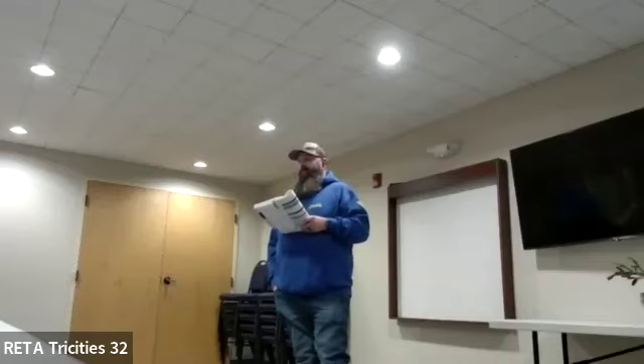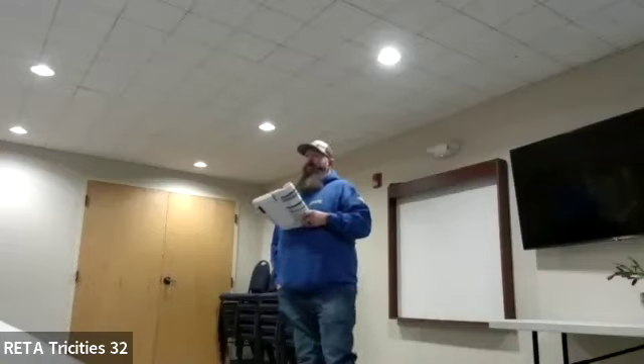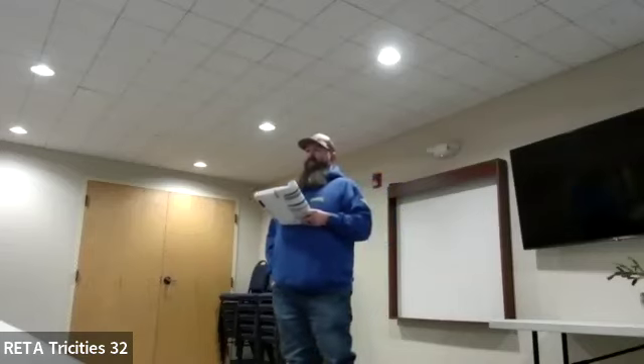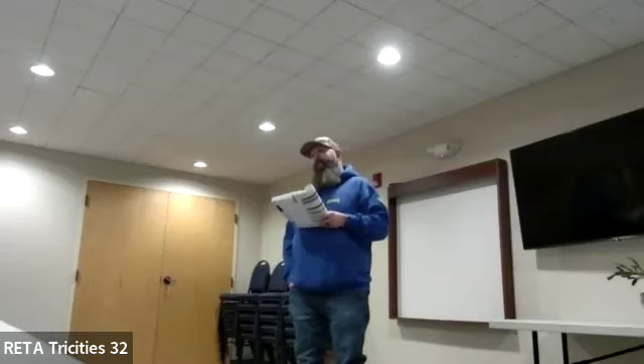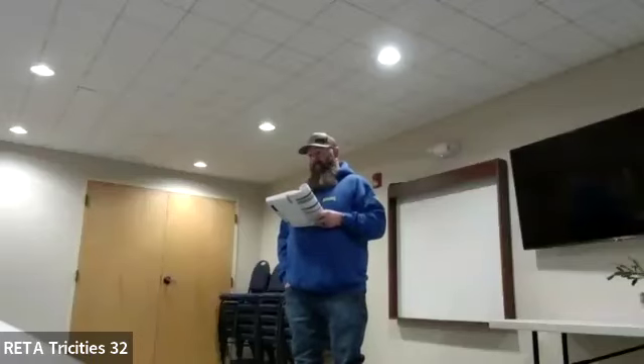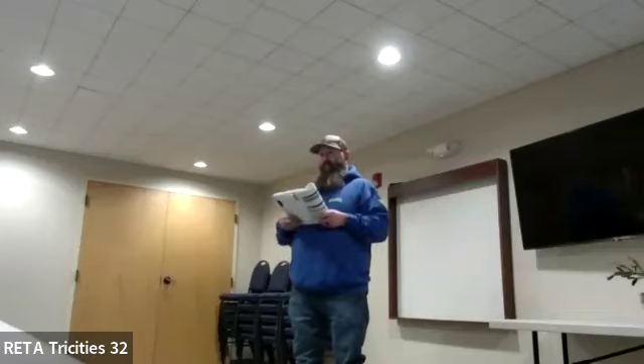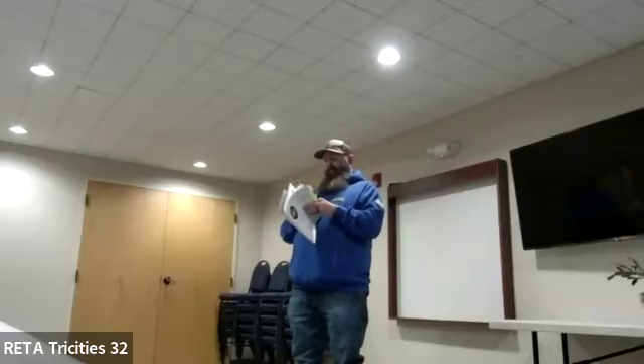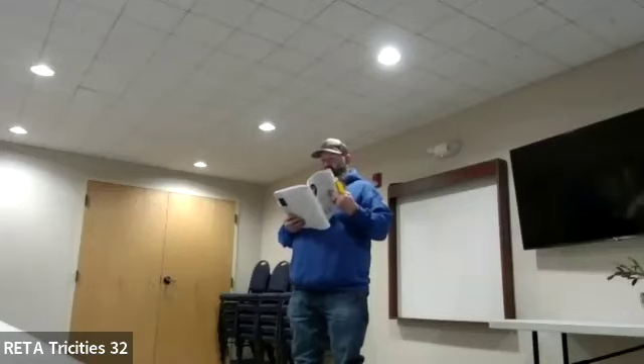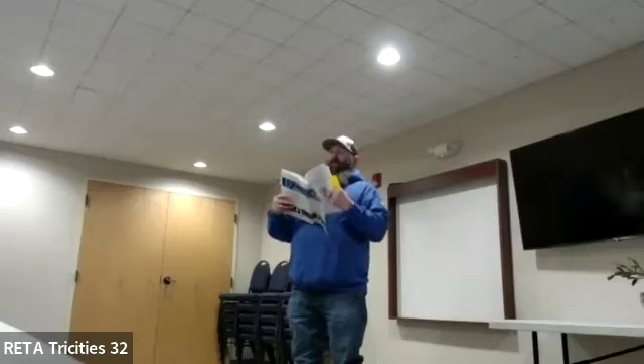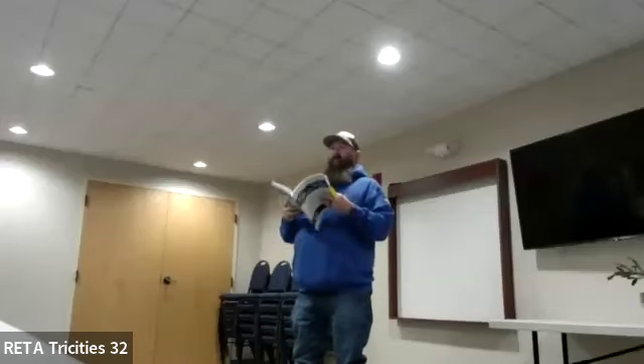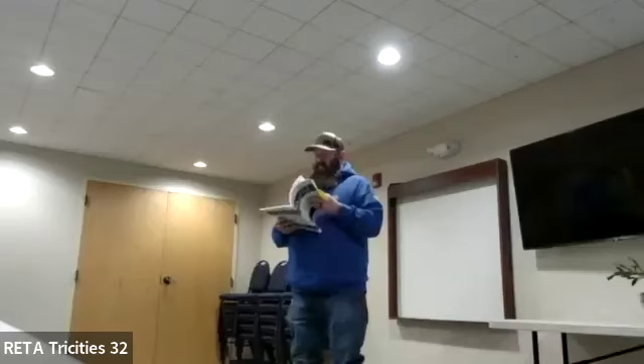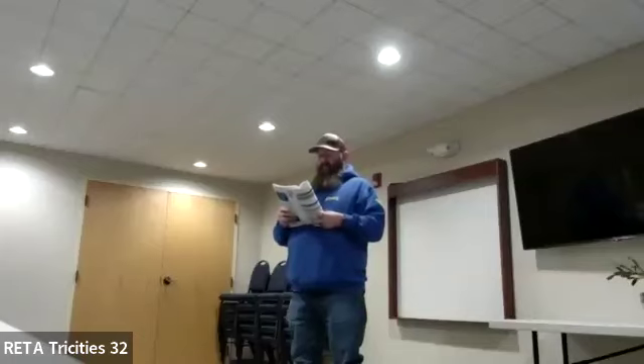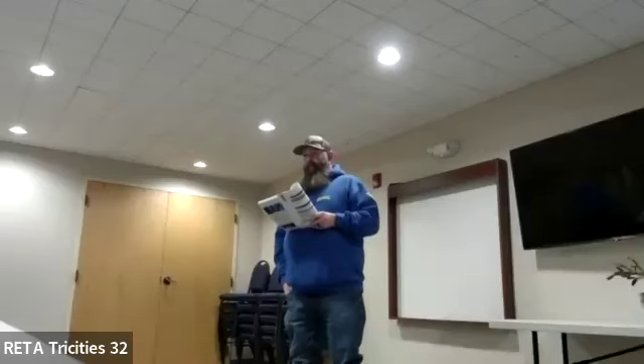I was going to say something here on that. One of our clients just had an issue with OSHA, and it was regarding eyewash. The system needs to supply 20 gallons a minute for 15 minutes of tepid water. That's what the eyewash has got to do. What's tempered water, like 85 or something? So 85 to 110. And I thought, holy crap, 110 degrees. If I'm in a freezer and I come out and have to wash myself off and I hit myself with 110 degree water, it's almost going to burn you. Yes. But I was surprised at how much time they wanted, how many gallons a minute.